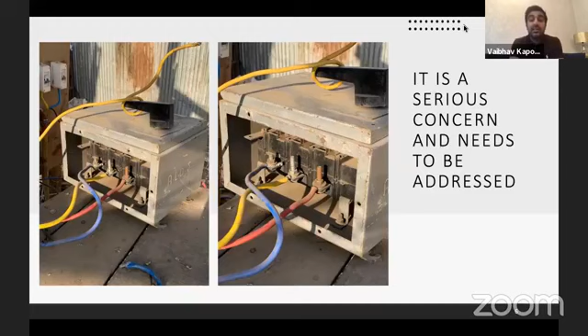So what is it that usually goes wrong with electricity? Firstly, as shown in those slides, inadequate or undersized wiring. We work a lot with generators and house power, so until the wiring is adequate, the genset can be of the highest capacity, but the power is still being taken from the wires. If there's inadequate or undersized wiring, it will cause overheating and possibly fire. Second point, overloads. What are overloads? There's a certain capacity a genset can take, a certain capacity a wire can take. If you try to put more load on something, it will overload, and ultimately that also leads to...